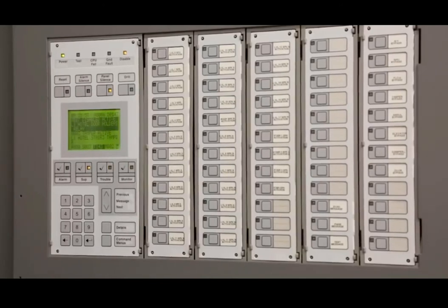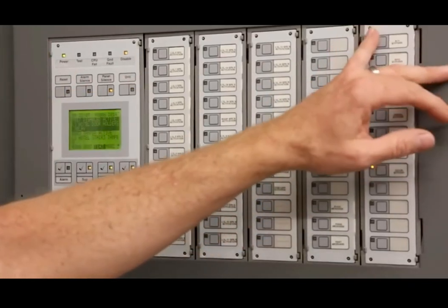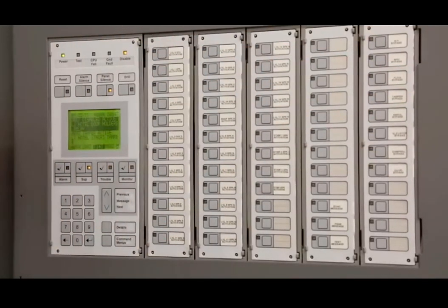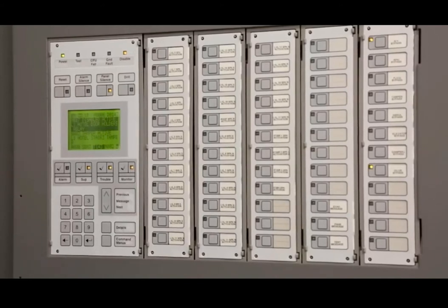I will say one thing though, if you are in alarm, do not bypass when you're in alarm. It will be a problem, okay? Only bypass when the panel is out of alarm. For instance, if you bypass the AVs in alarm and you go to reset, you're going to be re-triggering again because you're trying to tell it to stay out and then you're doing it again.